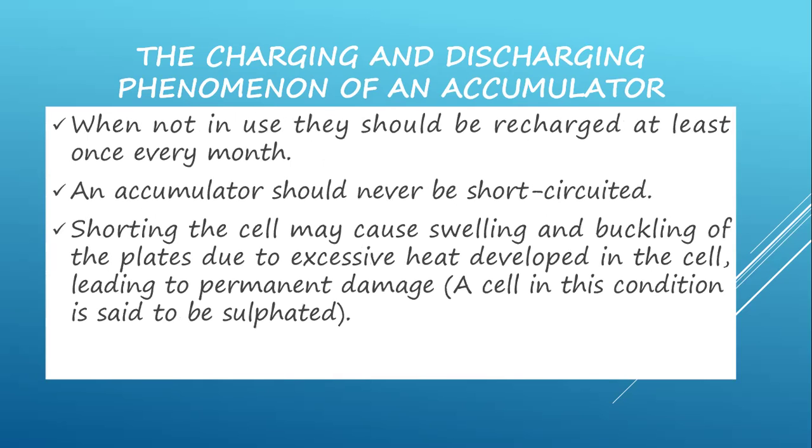When not in use, these lead acid accumulators should be recharged at least once every month, and the accumulator should never be short-circuited. Shorting the cell may cause swelling and buckling of the plates due to the excessive heat developed in the cell, leading to permanent damage, whereby a cell in this condition is said to be sulfated.